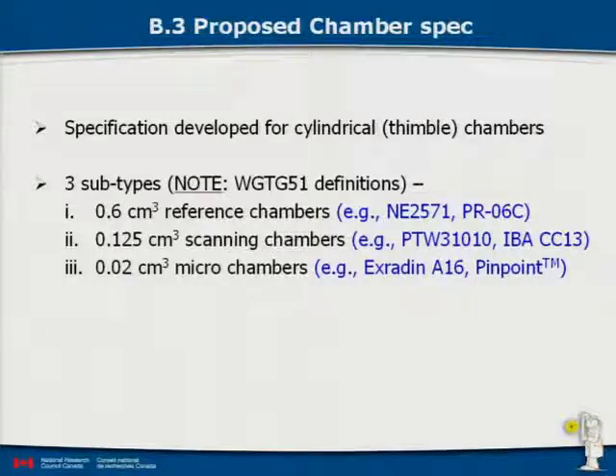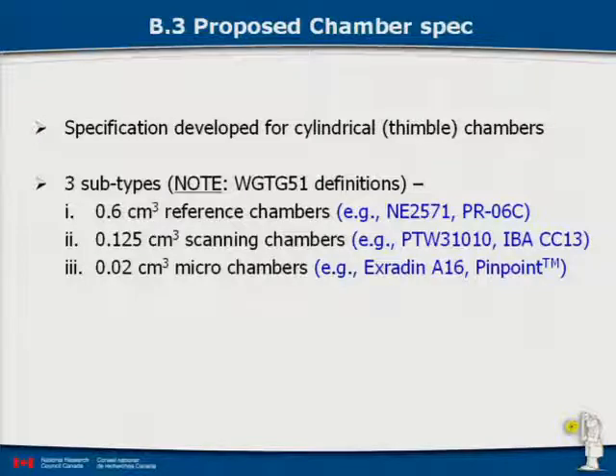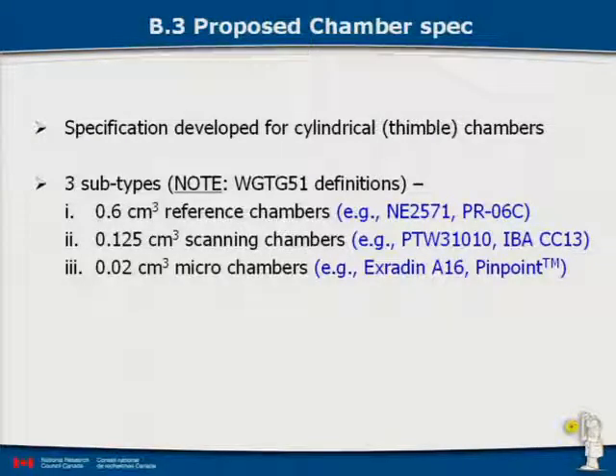The addendum is developing a proposed chamber spec for a reference class ionization chamber. Three subtypes are defined: 0.6 cc reference chambers — the standard NE2571, PR06C, A12; 0.125 cc scanning chambers used for commissioning, such as the CC13 and PTW31010; and microchambers defined as 0.02 cc or less — the A16, PTW pinpoint chambers, and IBA CC01. When I'm talking about reference, scanning, or micro, keep those definitions in mind.